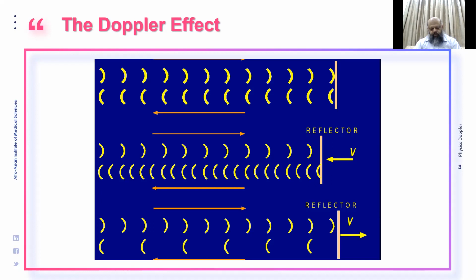For instance, if we have assigned red color to the structures which are moving towards the transducer, then the blood flow towards the transducer will appear as red on our machine. And if the particles are moving away from the transducer, which means the flow is away from the transducer, they will appear blue.